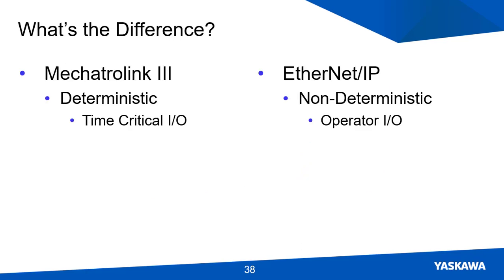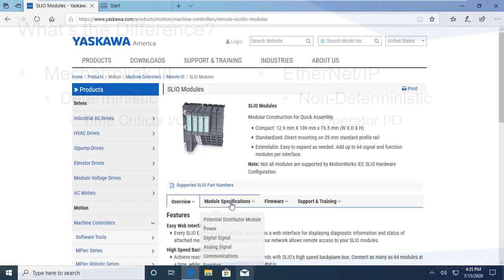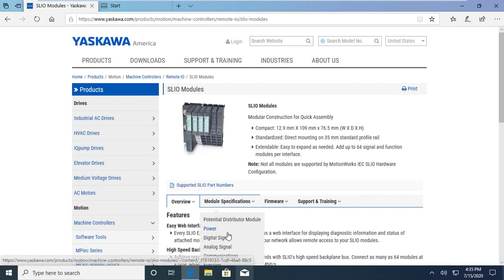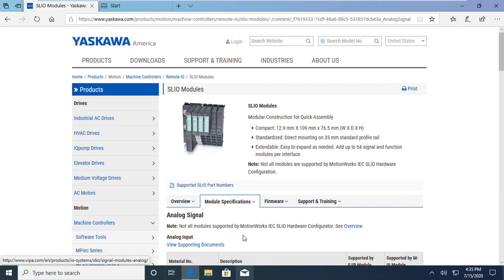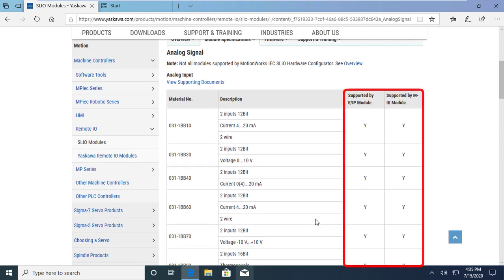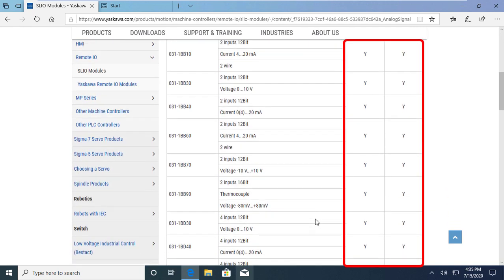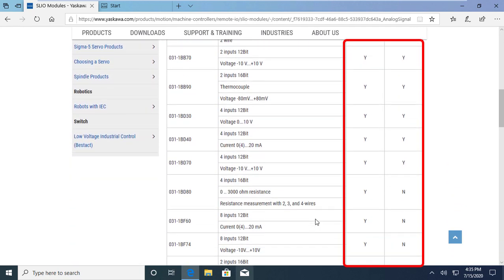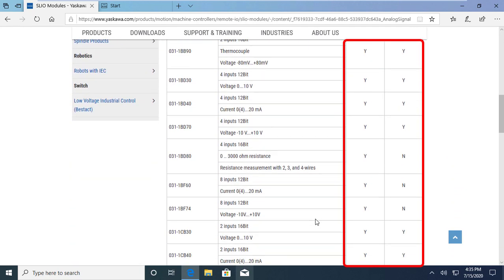So in this case, Mechatrolink 3 should be considered for time critical IO, compared to Ethernet IP which can be used for non-critical or operator IO. These two interface modules also have varied support for some of the function modules, as seen by the following table that you can find on Yaskawa's website.